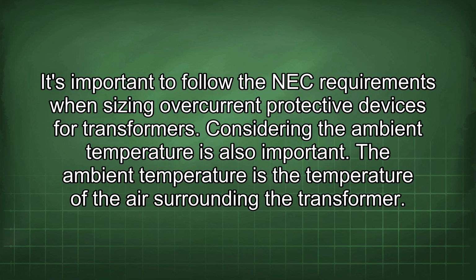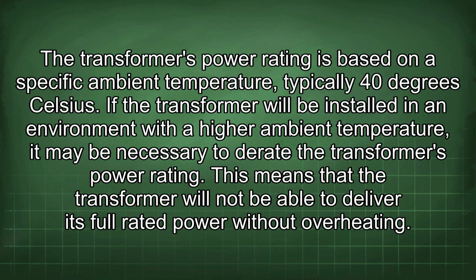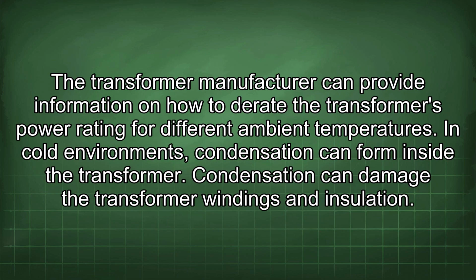Considering the ambient temperature is also important. The ambient temperature is the temperature of the air surrounding the transformer. The transformer's power rating is based on a specific ambient temperature, typically 40 degrees Celsius. If the transformer will be installed in an environment with a higher ambient temperature, it may be necessary to derate the transformer's power rating. This means that the transformer will not be able to deliver its full rated power without overheating. The transformer manufacturer can provide information on how to derate the transformer's power rating for different ambient temperatures.